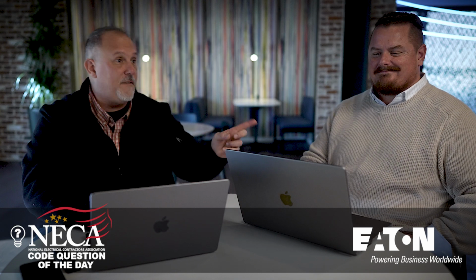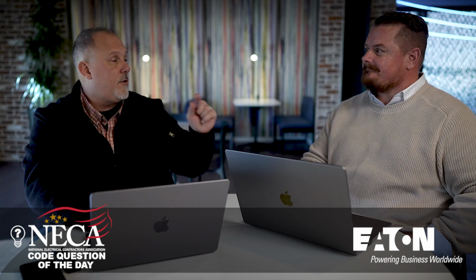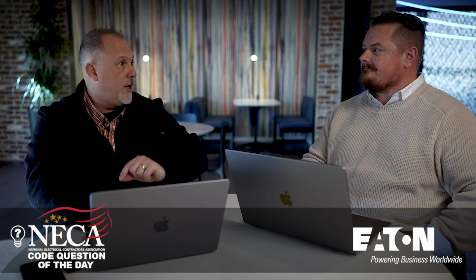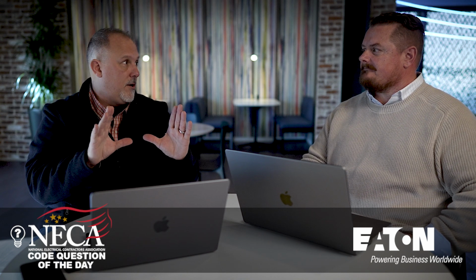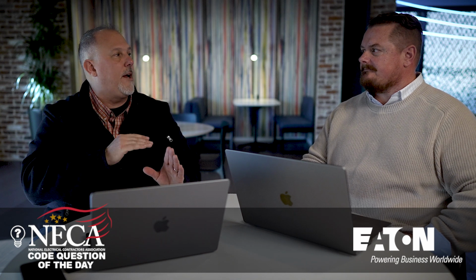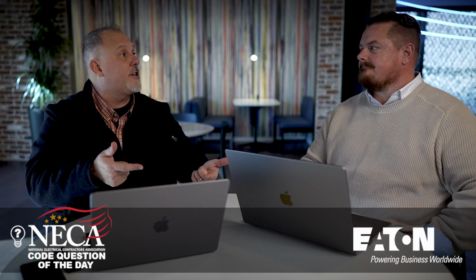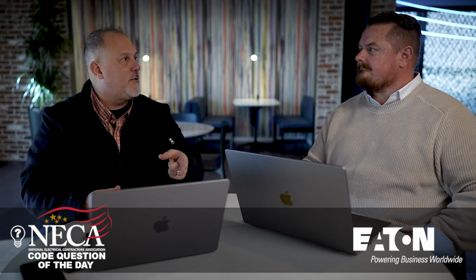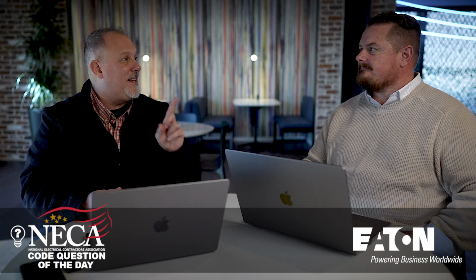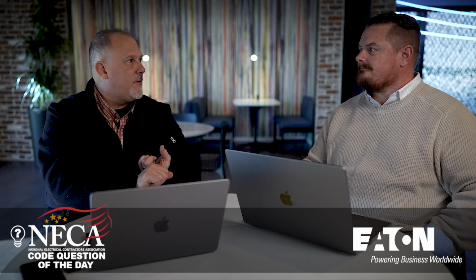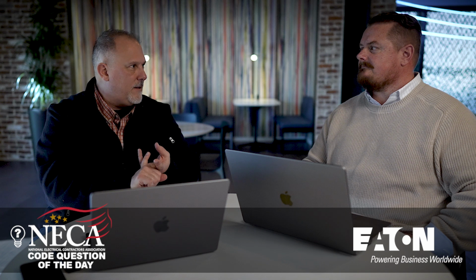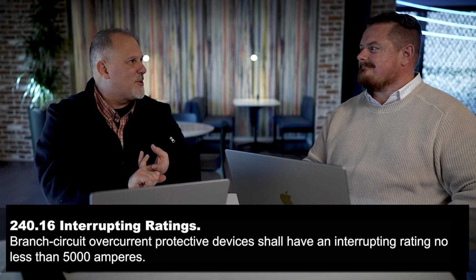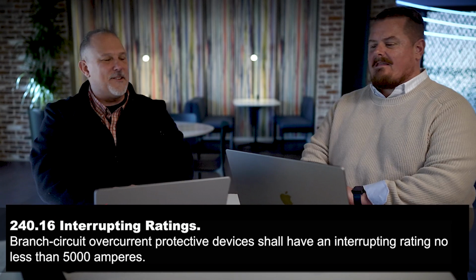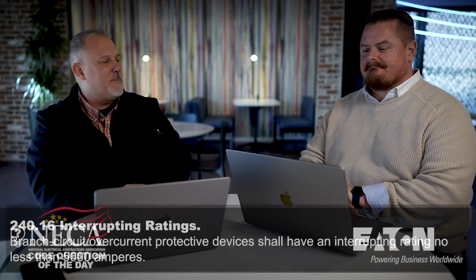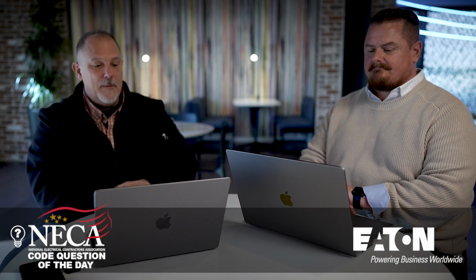So, yes, the UL 508A, the standard for industrial control panels, has a table of the default short circuit current ratings of various pieces of equipment that you'll find in an industrial control panel. The problem I have with that table is they call it a short circuit current rating, yet for a circuit breaker that's not labeled, it's 5K. For a fuse, it's 10K. Well, fuses and breakers don't have a short circuit current rating. They have interrupting ratings. So I have to bring that up to guys like Robert Osborne and the other guys at UL just to dig them a little bit. And Dan Easer, he's on 508.